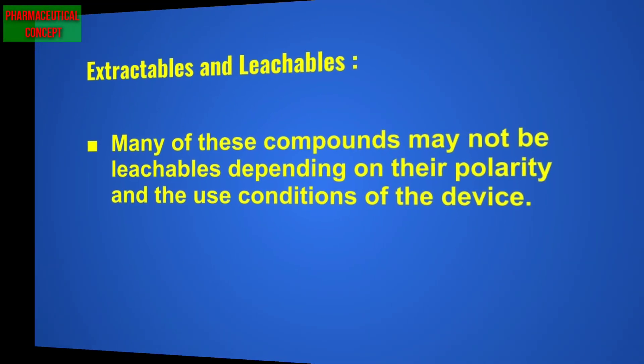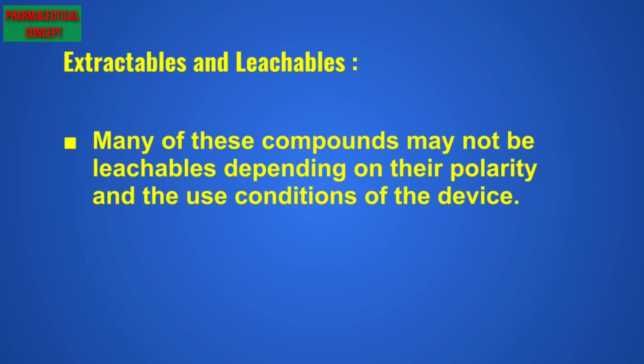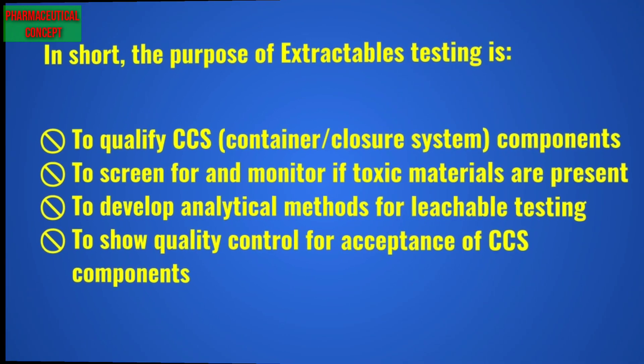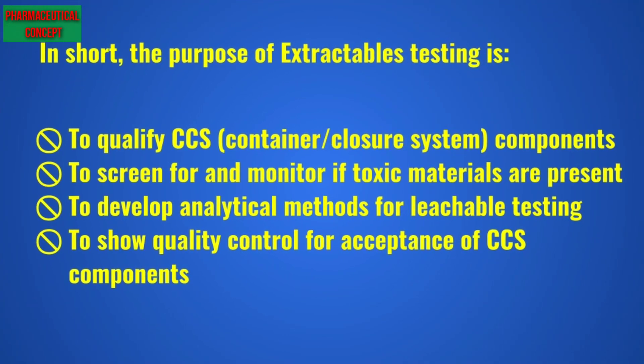Many of these compounds may not be leachable depending on their polarity and the use conditions of the device. In short, the purpose of extractable testing is to qualify the CCS — that is, the container closure system component — to screen for and monitor if toxic materials are present, to develop analytical methods for leachable testing, and to show quality control for acceptance of CCS components.